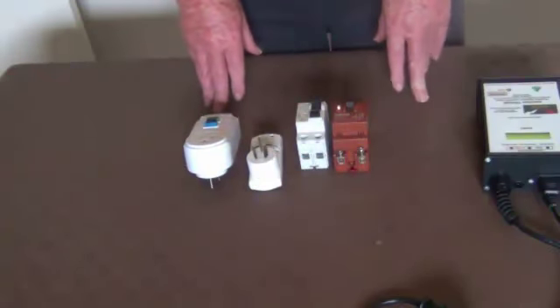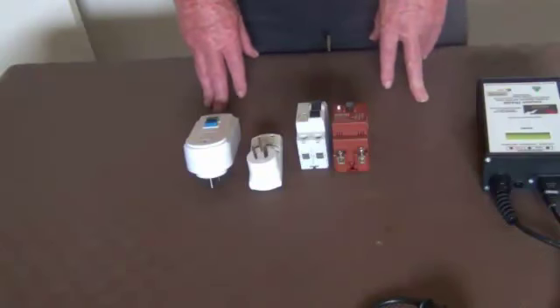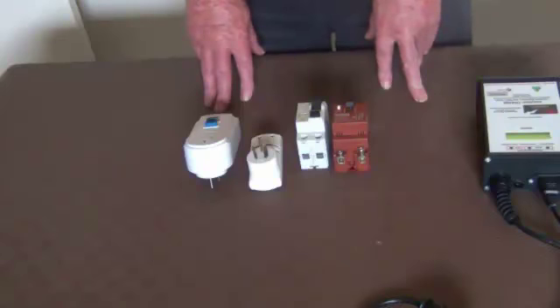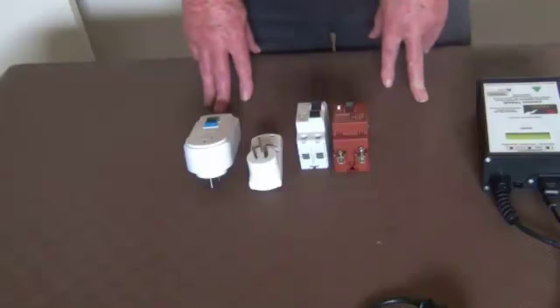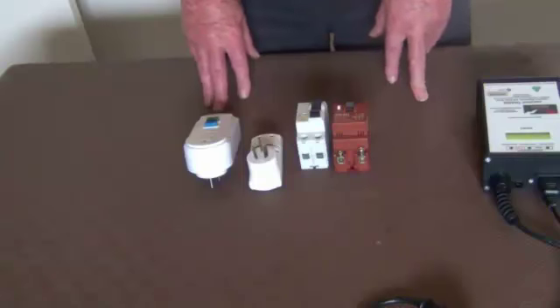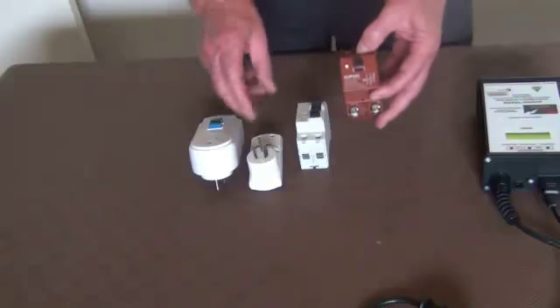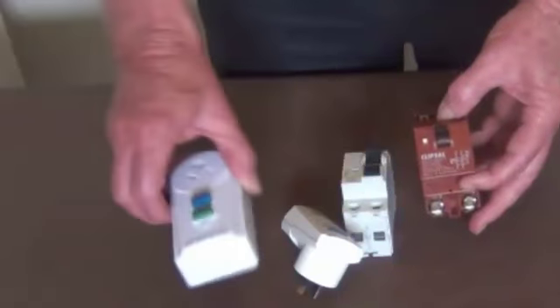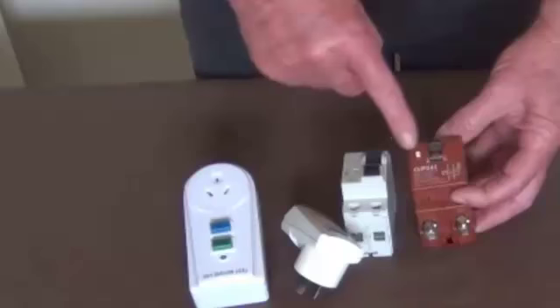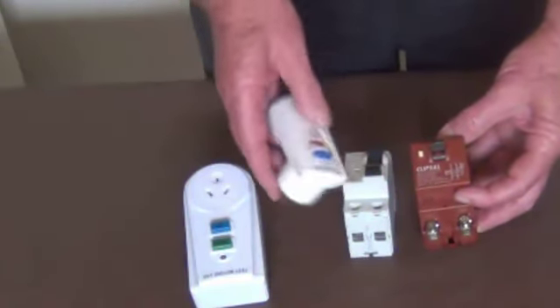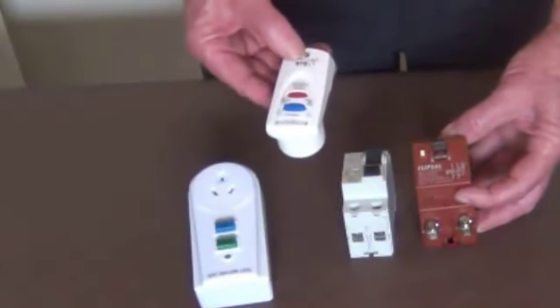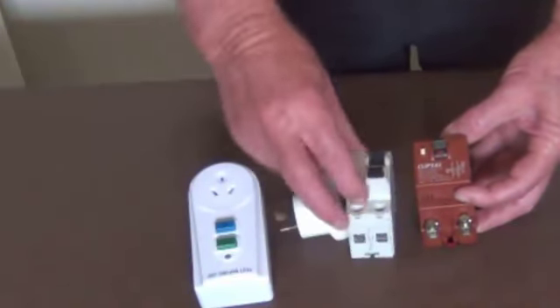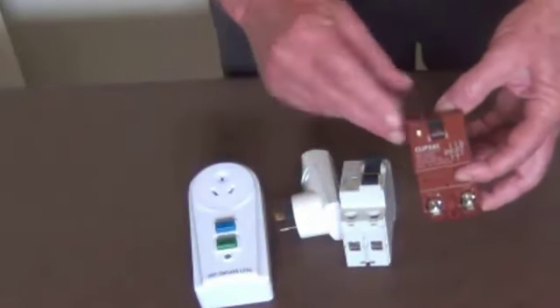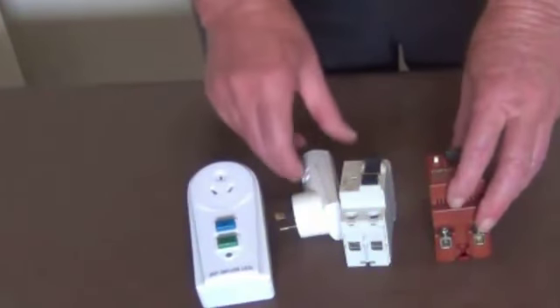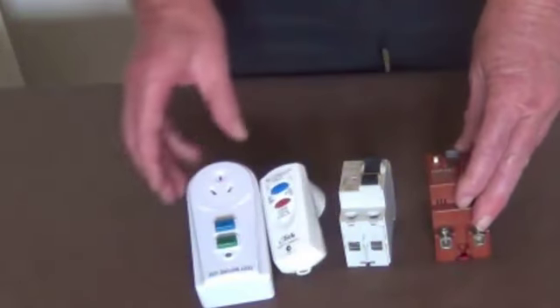These are the ones that you guys will be mostly interested in. These are RCDs, differential protection, safety switches, earth leakage circuit breakers, whatever you like to call them. They've got a million different names, but they all do the same job and they will all work in a very similar manner. I'll give a brief description after this on how they work, but for now we'll just assume that they do. Every RCD, no matter what type, how big it is, what the current rating is, has things in common. They protect people. And they all have a test push button of various sorts. There's a little blue one with a little T on it. This one is a red one with a test on it. This one is a black one with nothing on it. And this one is a white one with test. As I said, they'll come in a variety of sizes. This is just a representative sample of some that you might find in the workshop at any one time.